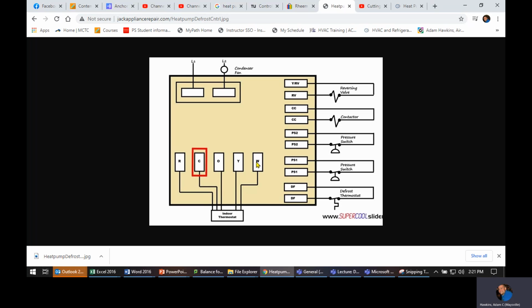Now, what is W for? When the system goes into defrost, a few things have to happen. So this system's running in normal heating mode. It's just doing its thing. It's projecting heat inside that it picked up from outside. Red is powering this board. Common is sending power back, or neutral back. Orange is telling it what position to be in. Yellow is telling it that the compressor needs to run or that it doesn't. When it goes into defrost, this reversing valve is going to switch positions. So if it's energized to heat, it's going to de-energize. If it's de-energized to heat, it's going to energize. So whatever it's doing to get it into heating mode, it's going to do the opposite, which essentially puts the system back in cooling mode.